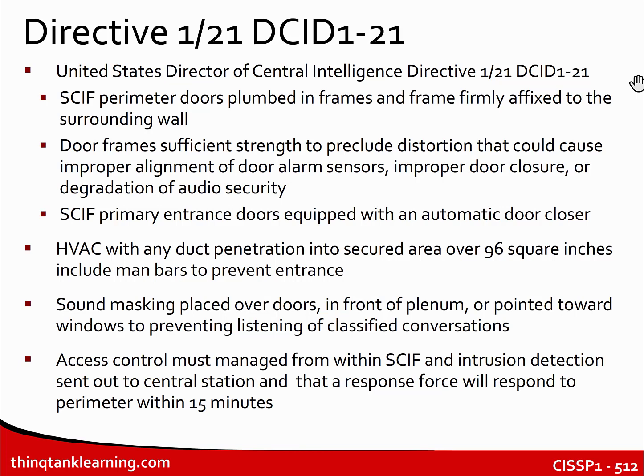The SCIF's primary entrance doors need to be equipped with an automatic door closer. The HVAC system, with any duct penetration into the SCIF over 96 square inches, has to be secured, including man bars—maybe we should call those person bars nowadays—to prevent entrance. And sound masking, I was being facetious there, but sound masking should be placed over doors, in front of plenum, or pointed towards windows to prevent listening in on classified conversations.